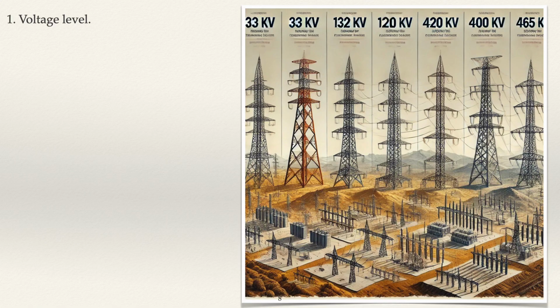Starting with voltage level. Though we have covered this topic in our initial chapters, to brush up, let us understand in brief. Voltage level is a critical subtopic in the design criteria of transmission lines as it influences the entire system's efficiency, safety, and reliability. Let's break it down. Transmission voltage. The operating voltage level of a transmission line is one of its key parameters, usually specified as 33 kV, 132 kV, 400 kV, or higher, depending on the project, determined based on factors like power demand, distance to be covered, and the grid requirements. For short distances and lower demand, lower voltage levels like 33 kV might suffice, while longer distances with higher loads require higher levels, such as 400 kV or 765 kV, to minimize transmission losses. Higher voltage reduces current for a given power, minimizing resistive losses and allowing more efficient energy transport over long distances.